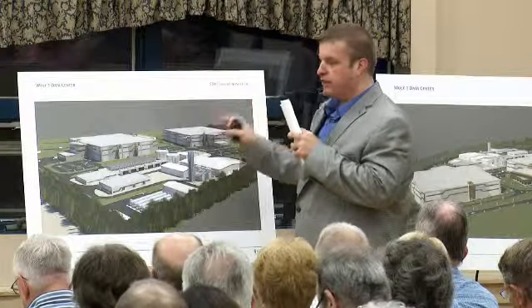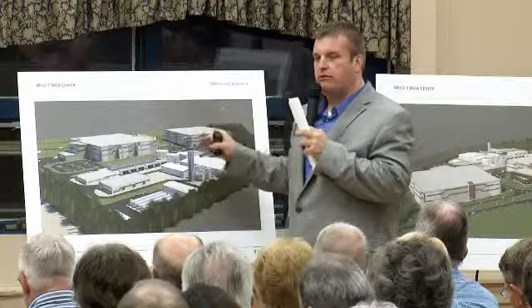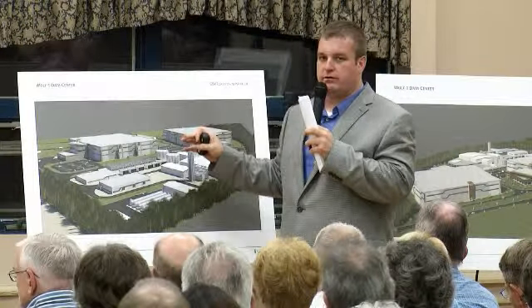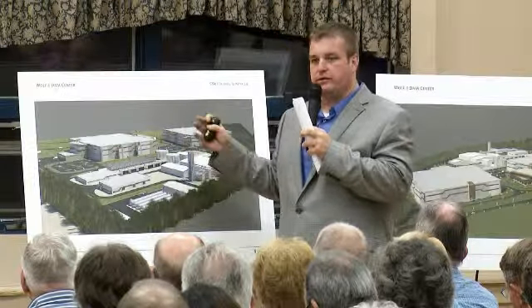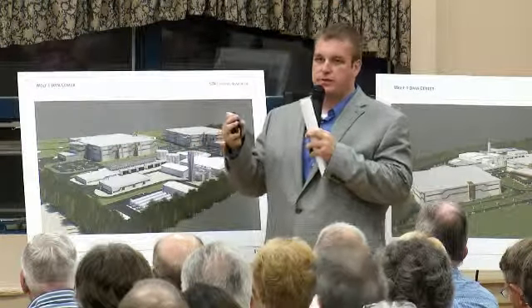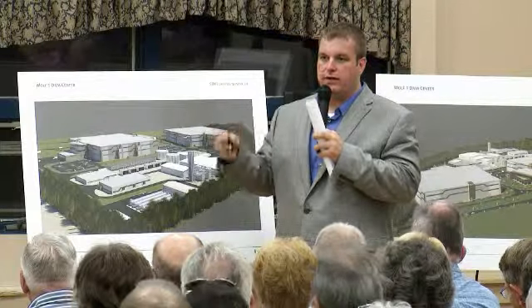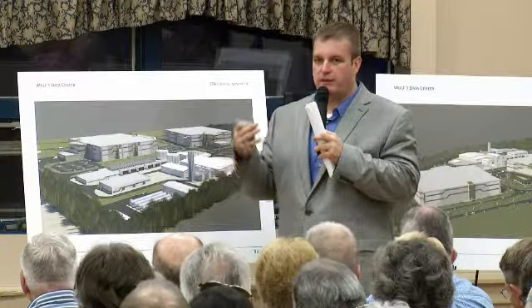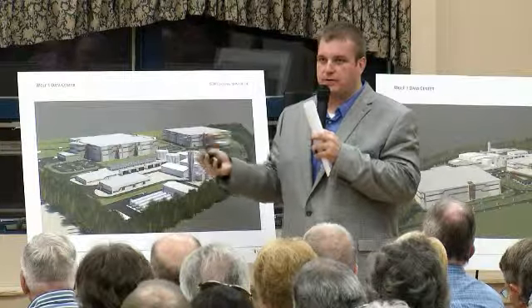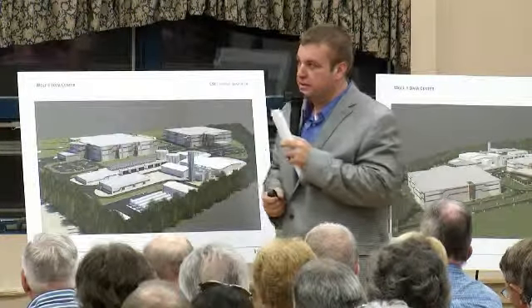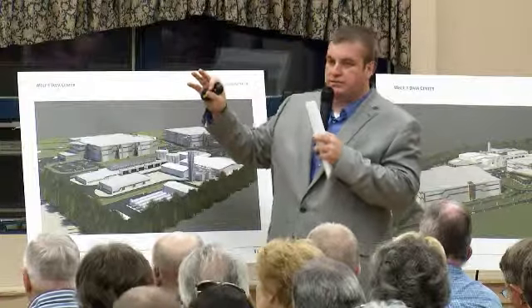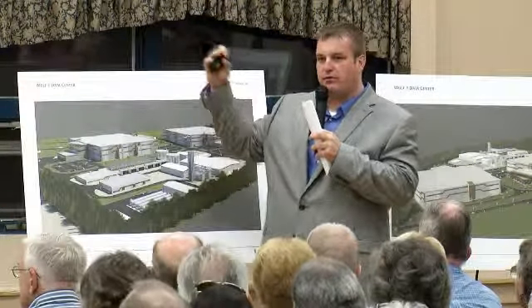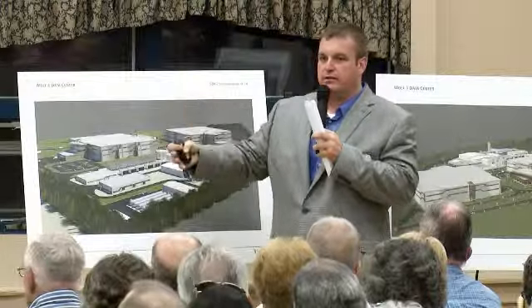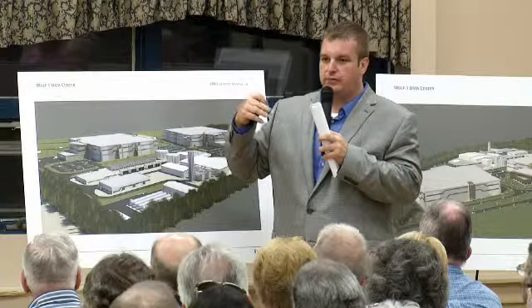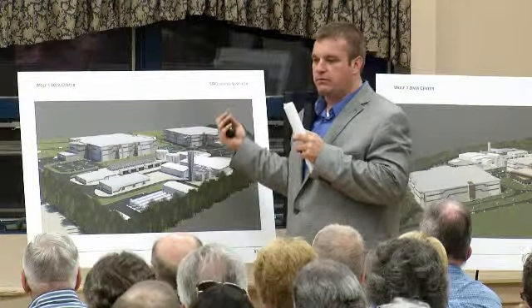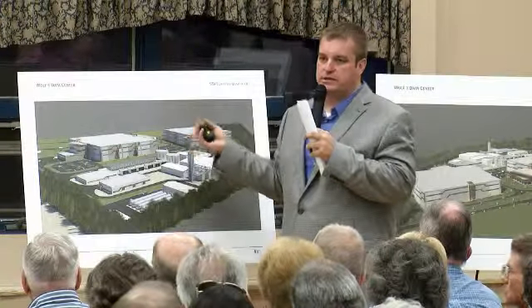Part of our innovative design is we've taken the battery backup part of a standard data center out of the process. In doing that, we need to provide additional generators to provide power, and those generators will be spinning all the time due to the nature of their gas turbines and gas reciprocating engines. So that capacity of 50 megawatts gives us our backup. If we have a failure on a primary generator, we can spin up the other generators and provide backup, because our data center's business model is providing 100% uptime to our customers.